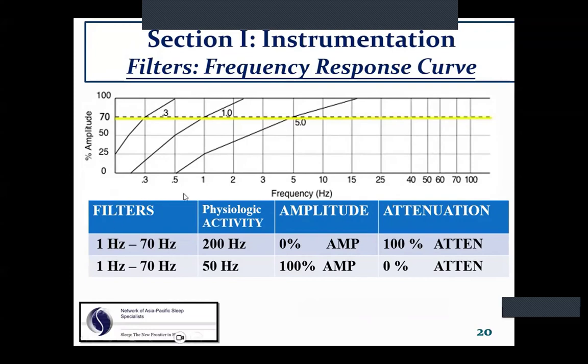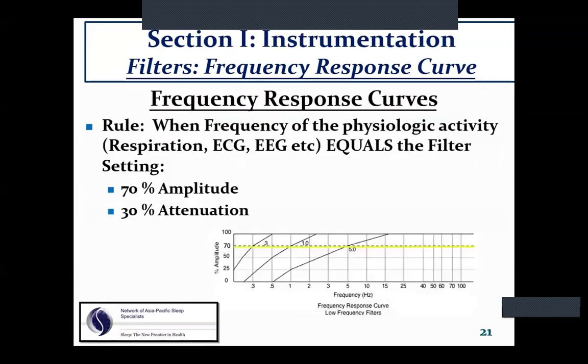So let's go over here to a 1 hertz waveform on the x-axis. We track that up, and if we have a 1 hertz filter setting, this yellow line is telling us we don't see 100%. We see 70% amplitude, 30% attenuation or amplitude decline. So the basic rule is when the frequency of the physiologic activity, respiration, ECG, EEG, equals the filter setting, you will always have 70% amplitude and 30% attenuation.